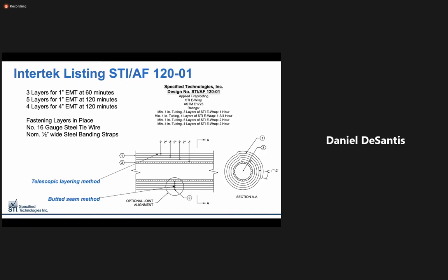This particular test system was tested by Intertek, listing number STI AF 120-01. This is an all-encompassing conduit system for the 2-hour F-rated protection of a conduit. This system allows for 2 different methods of installation. The telescopic method, where layers are offset by 2 inches and overlapped horizontally as layers are installed, as well as the butted seam method, where all layers are applied in 24-inch wide sections and butted against the next.